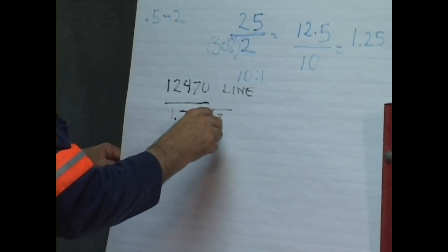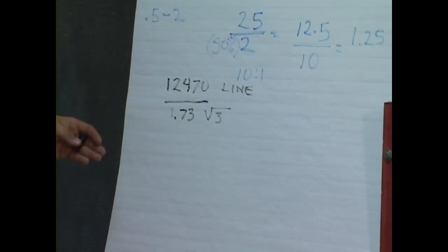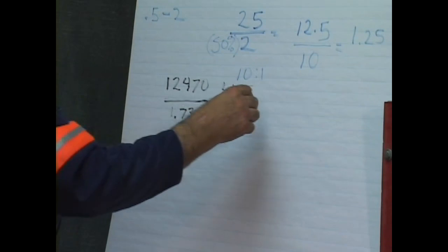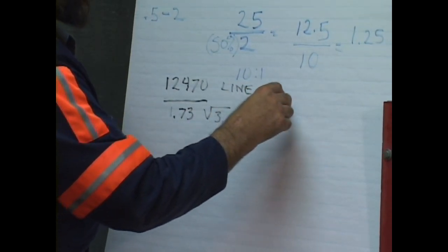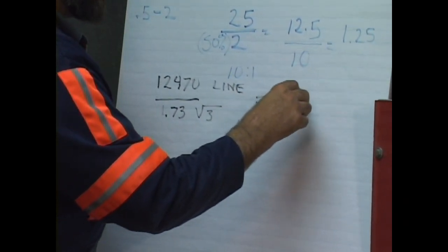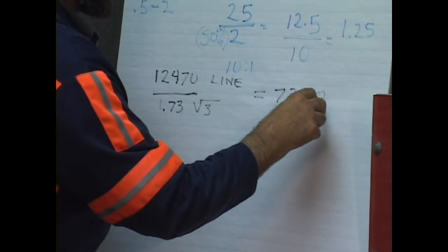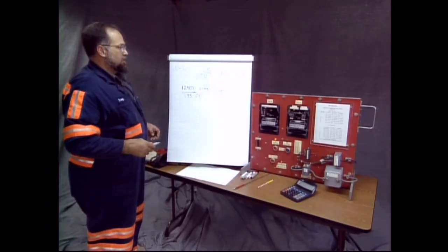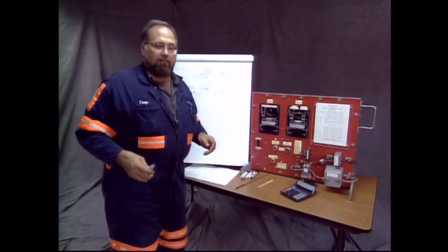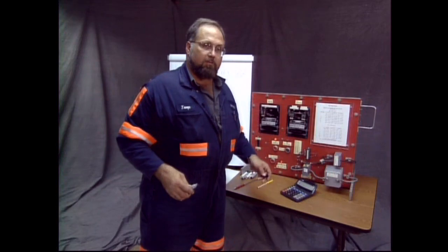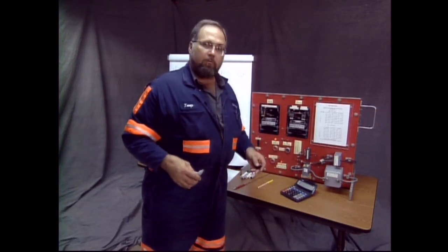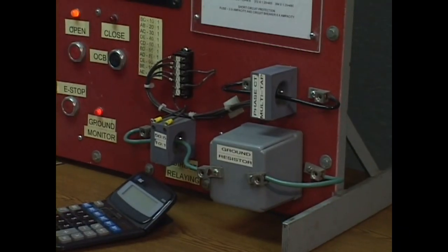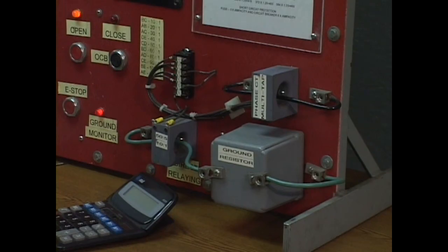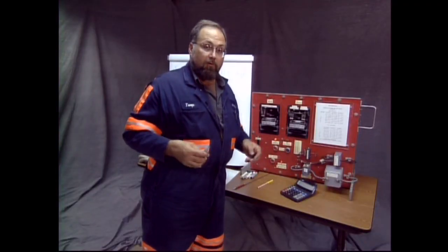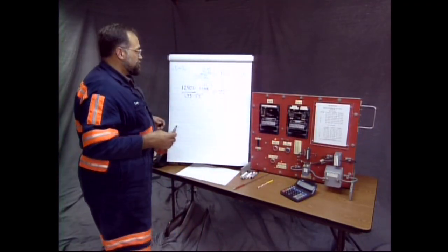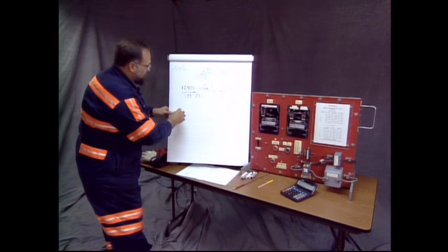square root of 3. We're going to divide 12,470 by the square root of 3, and that'll give us a phase voltage of 7208. That's one phase. Now our goal is to have a ground resistor appropriately sized to convert as much of 7,208 volts to heat as possible in the event of a ground fault. So let's use Ohm's law.